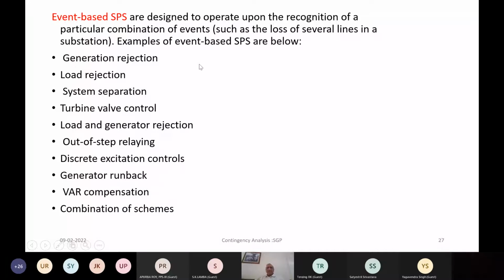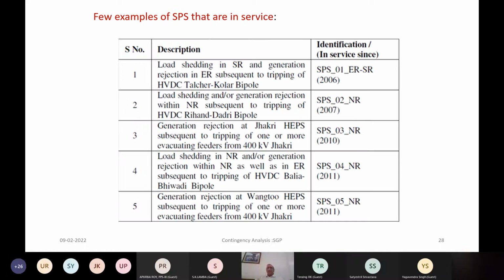Instead of tripping of generators, you can run back the generation. So running back of the generation could be by the action on the turbine control valve on the steam turbines, or it could be inlet valve control on the hydro turbines. We can have actions due to out of step relaying. Again, this is something which we'll discuss in the afternoon more in detail. Excitation controls, generator run back, VAR compensators to be triggered automatically, or a combination of all these different types of schemes. So all these can be done as a special protection scheme.